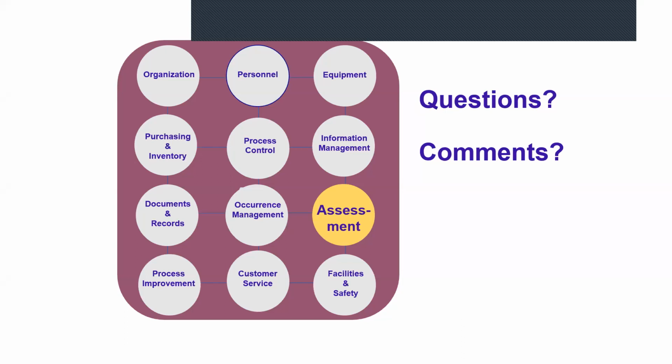You want to be very close to your mean, but that's the variability that you're allowed. But if you have too much variability and you get out of control because you didn't do maintenance or whatever, and that internal quality control went 3 SDs, then you know that you have to do something to your instrument to maintain it in control. So that's why it's so important for us to know what our expected variability is for every analyte. I don't know if that answered the question.